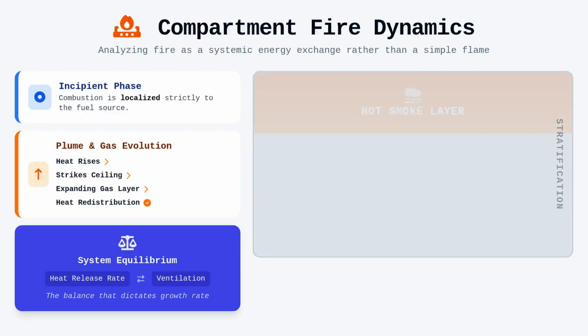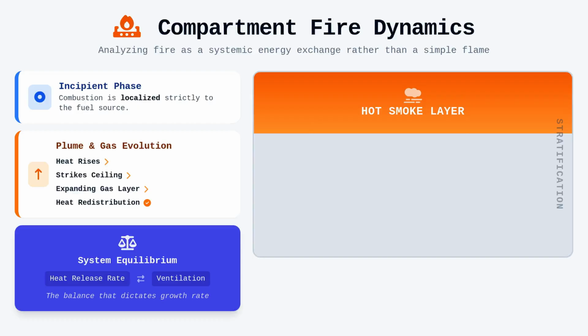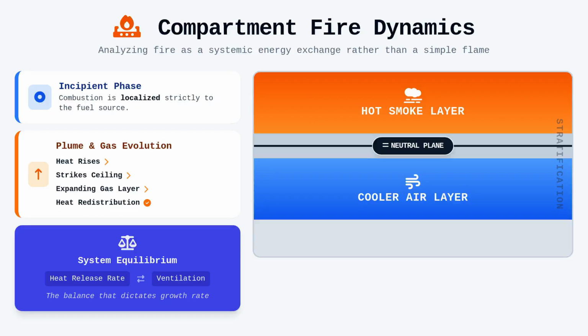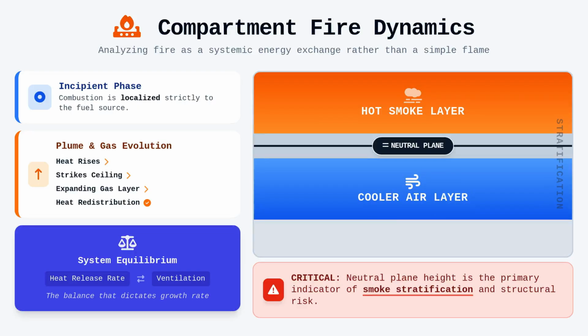If we consider the compartment as a two-zone model, we identify an upper hot smoke layer separated from a cooler, clearer lower layer by a neutral plane. This neutral plane is the pressure boundary where atmospheric pressure equals the pressure of the hot gases, and its height is a primary indicator of smoke stratification. Maintaining control over this vertical layering is often the difference between a manageable incident and a total loss of structural integrity.